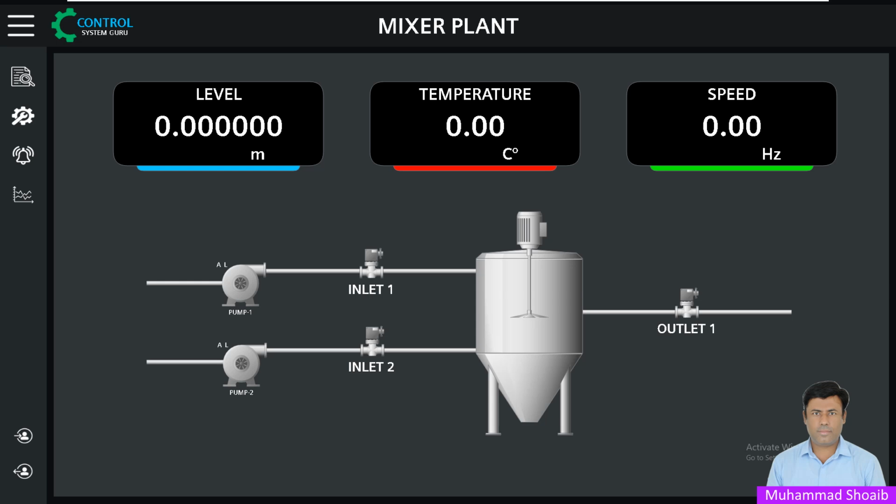What is the difference between alarm and event? Alarms notify the operator of abnormal or critical conditions that require attention, such as a motor fault or high temperature. Events, on the other hand, are simple logging entries for information or operator actions, such as the operator changing the set point, a recipe load, auto/manual or local/remote actions, or executing some commands.